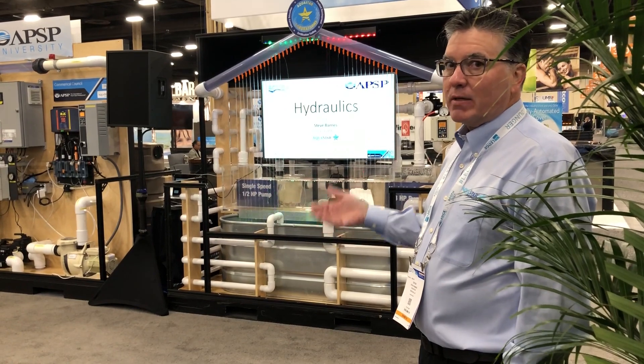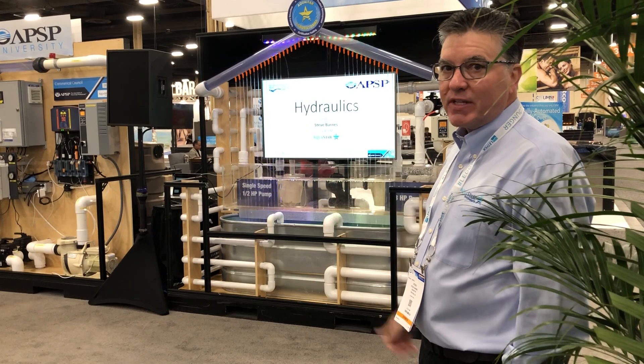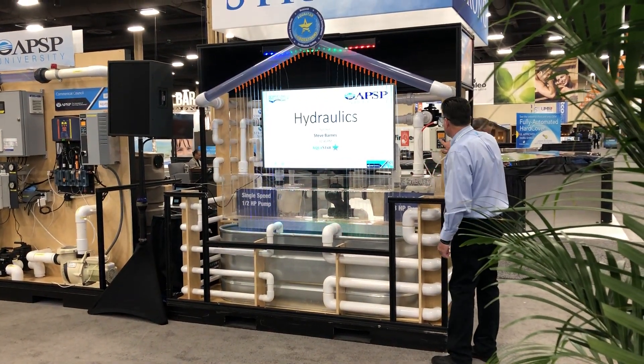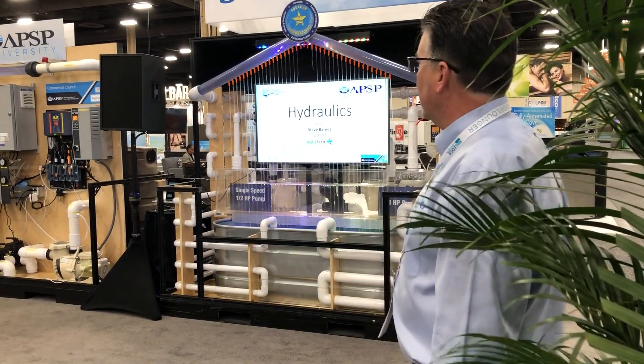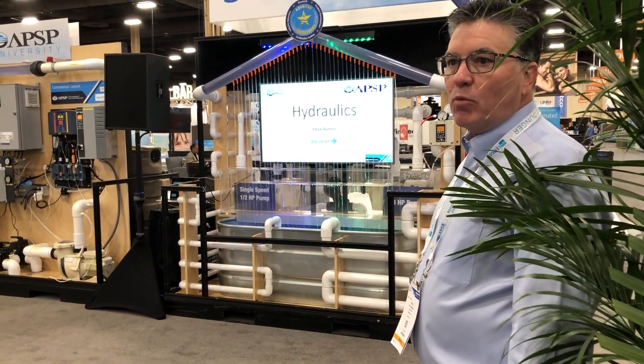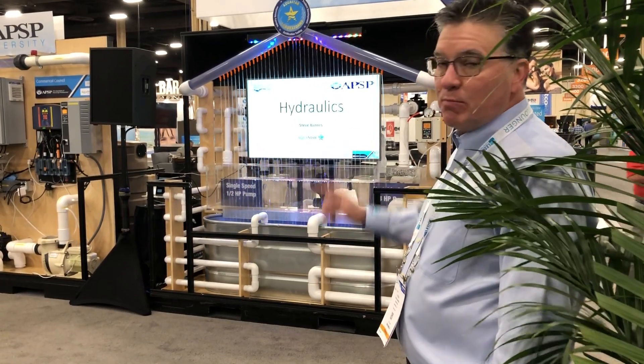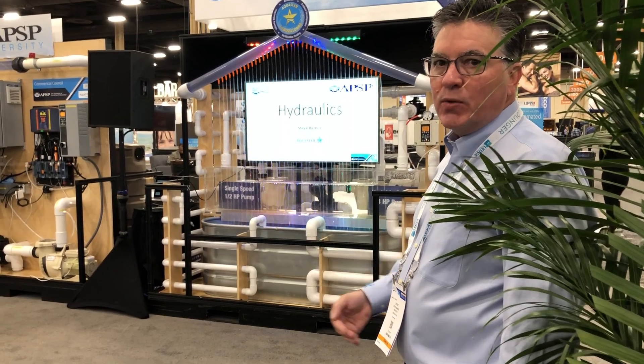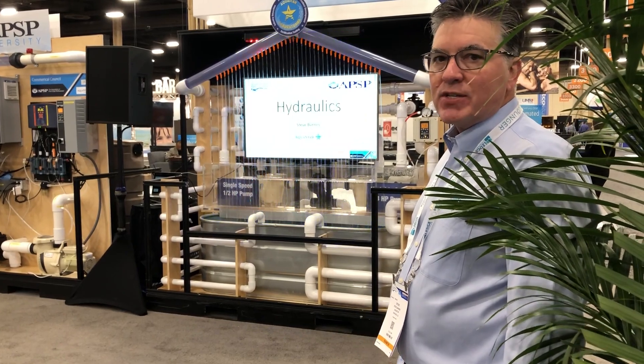Small pipe causes lots of restrictions. Now we have the variable speed pump so I'm going to ramp it up to fix this. It went from 1200 RPM to 1700 RPM to make this work. The watts jumped from 103 to 285. So that small pipe, every time you're running it, costs two and a half times more than buying the proper sized pipe — two and a half inch in this case.